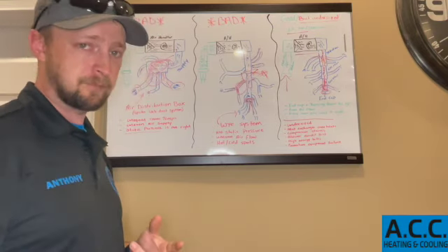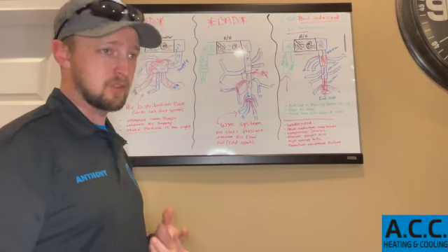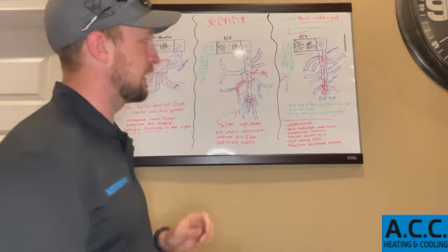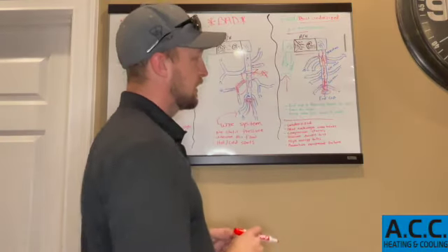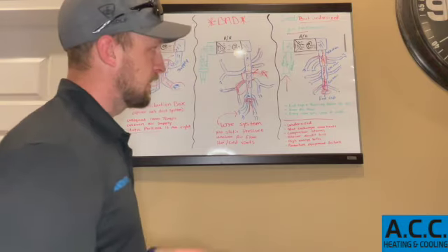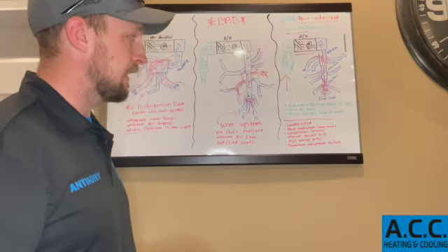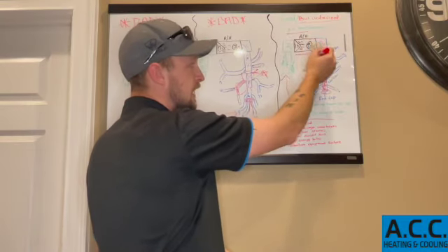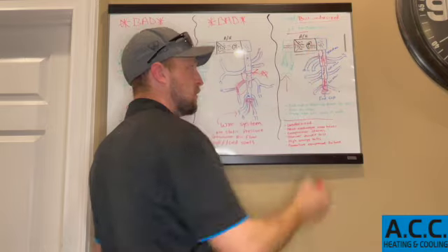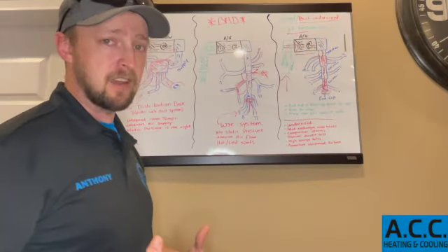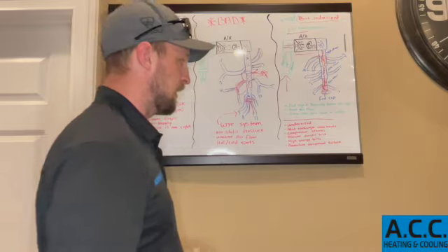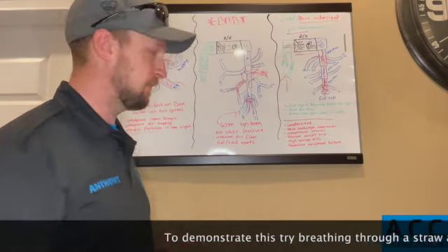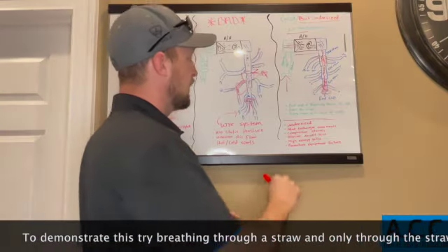The compressor starts to go out, premature compressor death, because of the flow of refrigerant. If it can't get enough air across this coil to get rid of the hot and cold air that this coil is producing on a heat pump, then your compressor starts to go bad. The blower that's in this unit here, if it can't pull 1,000 CFMs of air through there, then it's suffocating itself and the blower motor starts to go bad. Higher energy bills when it's undersized, and ultimately premature equipment failure.